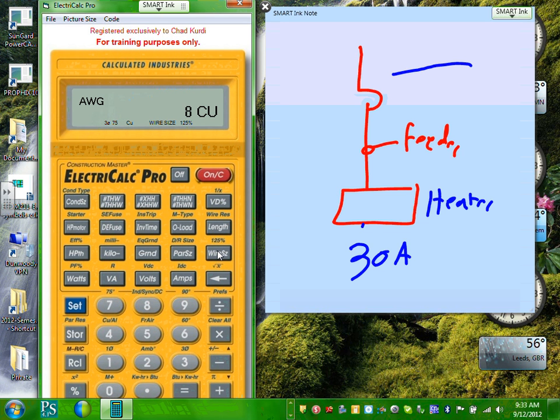We didn't do this for the panel because the panel, we match it to the overcurrent protection device. But if you have a load that's continuous load, like motors, you put the amps and put set wire size, it's sized based on 125, not just based on 100%. Can I have thumbs up, chat?